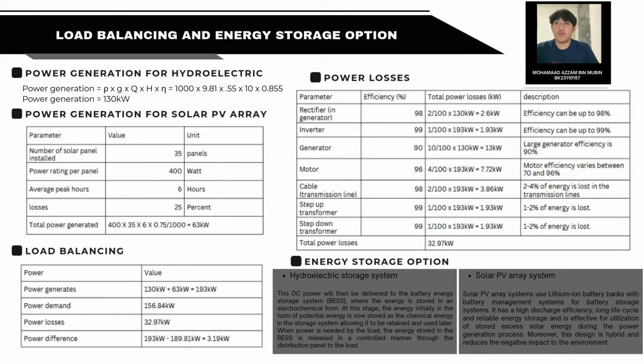For the estimation of power generation, the hydroelectric power generation is 130 kilowatts, while the solar PV array system is estimated at 63 kilowatts. We have also accounted for the power losses of 32.97 kilowatts caused by the rectifier, generator, inverter, and the transmission line. After calculating, we balance the generation against the demand and losses. We have maintained a positive power difference of 3.19 that will ensure the system remains stable even under load.